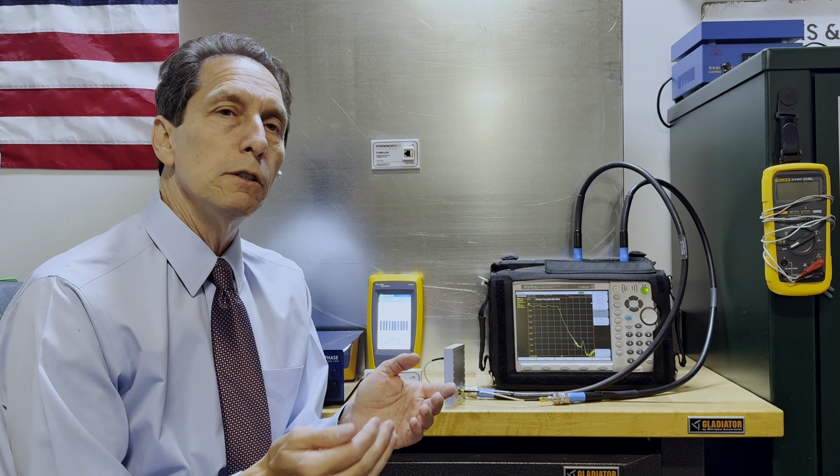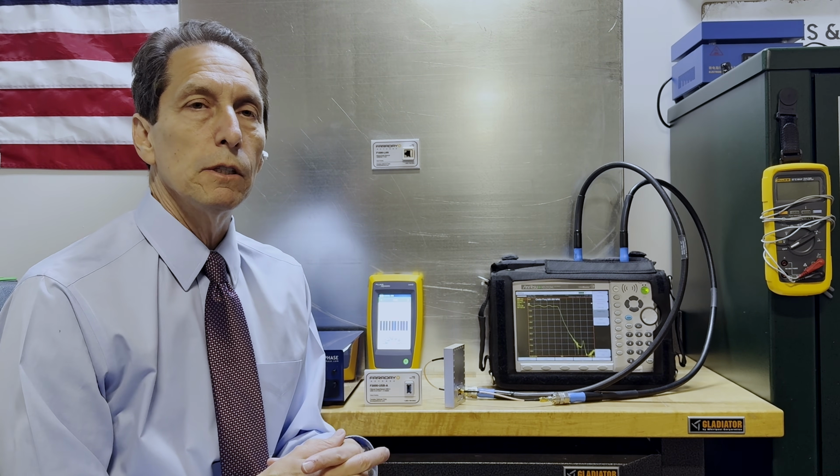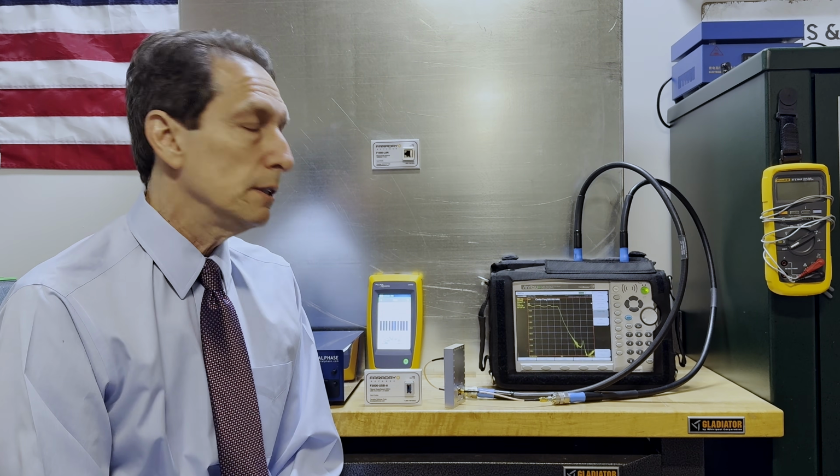So what I wanted to talk about today was, first of all, why these filters are important, and then how we validate our filters. So first, if you didn't have filters at all and you just passed signals through the shielded wall, you'd find it would greatly compromise the shielding of your space. If you had a 100 dB room, for example, something that had 100 dB of shielding, just passing a single wire through it might drop it to 50 dB. So it can greatly compromise it if you don't have filters on the walls. And you use filters for power signals as well as data filters. These filters are all for data. Power filters are typically much larger, and they're sized according to the amount of current and voltage that's needed.